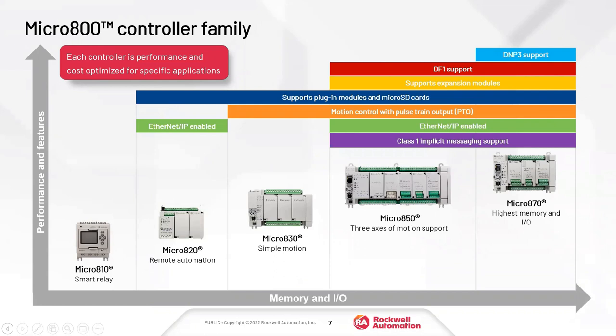The Micro 800 family is the general term for the full family. There are five different models scaling from the 810 — which is like a smart relay — up to the Micro 870. The first big news is that the Micro 830, the model in the middle, is going to become a discontinued product fairly soon, sometime in the summer timeframe. The 830 was a strange sibling in that it didn't have an Ethernet port — just serial and USB — so it makes sense that Rockwell would discontinue it since the 820, 850, and 870 all support Ethernet.